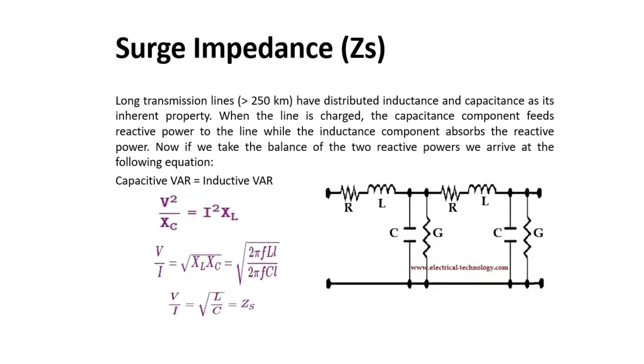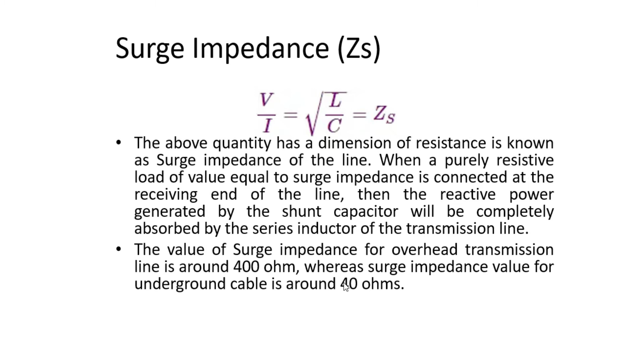It means that when we have calculated Zs, the surge impedance of the line, and we connect a purely resistive load of equal value to the impedance of the transmission line, then the reactive power generated by the shunt capacitor will be completely absorbed by the inductor of the transmission line. In that case the total maximum power is transmitted, that is the real power, because the reactive power is totally absorbed. The value of the surge impedance for an overhead transmission line is around 400 ohms, and for an underground cable it is around 40 ohms.